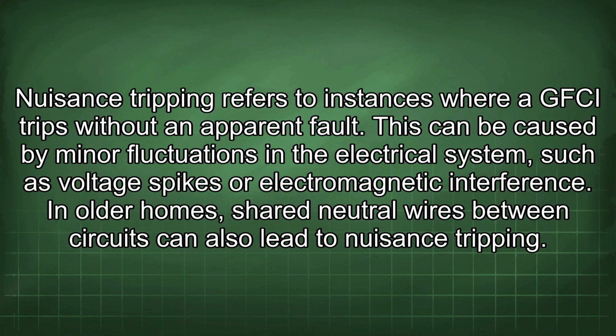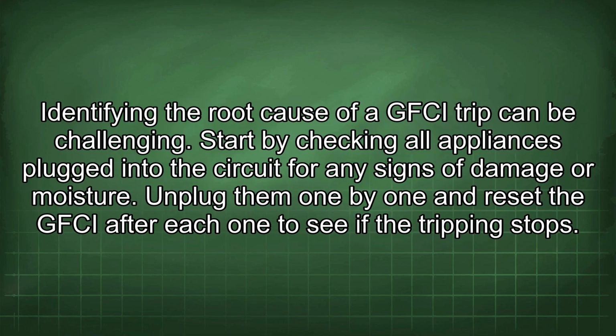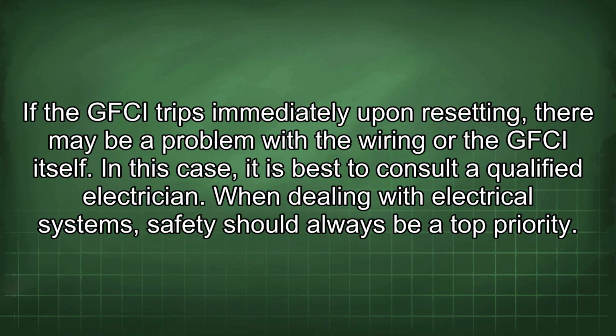Nuisance tripping refers to instances where a GFCI trips without an apparent fault. This can be caused by minor fluctuations in the electrical system, such as voltage spikes or electromagnetic interference. In older homes, shared neutral wires between circuits can also lead to nuisance tripping. Identifying the root cause of a GFCI trip can be challenging. Start by checking all appliances plugged into the circuit for any signs of damage or moisture. Unplug them one by one and reset the GFCI after each one to see if the tripping stops. If the GFCI trips immediately upon resetting, there may be a problem with the wiring or the GFCI itself. In this case, it is best to consult a qualified electrician.